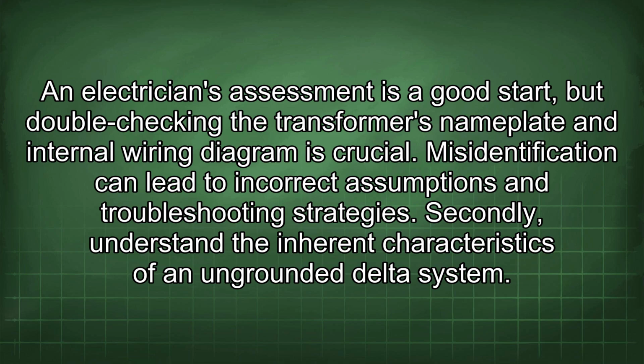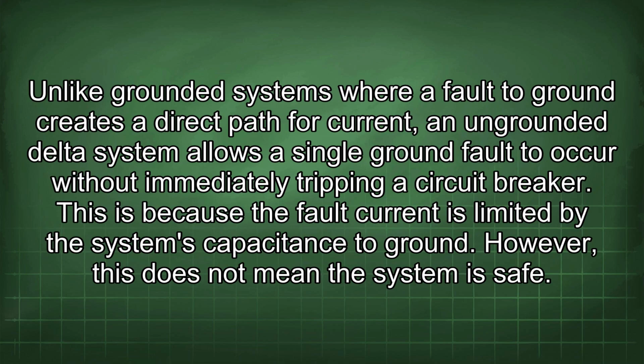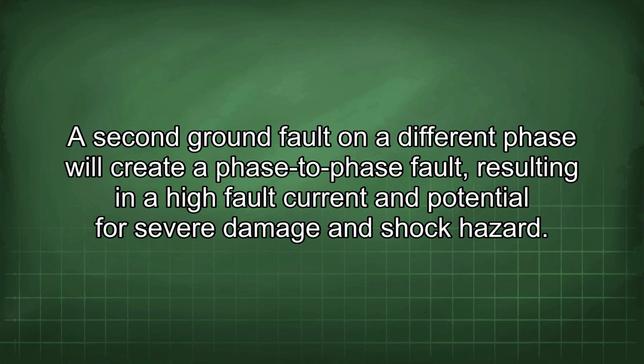Secondly, understand the inherent characteristics of an ungrounded delta system. Unlike grounded systems where a fault to ground creates a direct path for current, an ungrounded delta system allows a single ground fault to occur without immediately tripping a circuit breaker. This is because the fault current is limited by the system's capacitance to ground. However, this does not mean the system is safe. A second ground fault on a different phase will create a phase-to-phase fault, resulting in a high fault current and potential for severe damage and shock hazard.